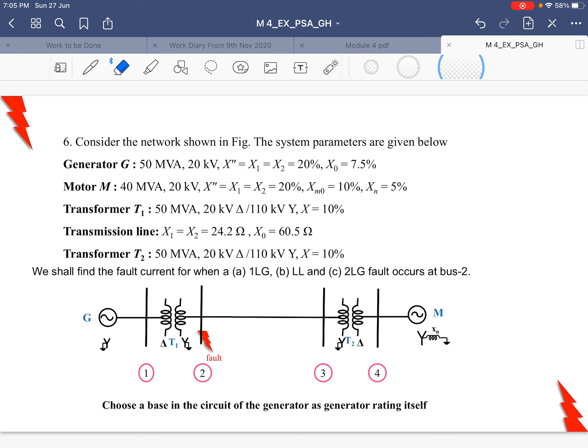What I have taken here is 50 MVA, 20 kV as the base quantity in the generator circuit. And here the transformer is 20 kV to 110 kV. The base voltage is transferred as 110 by 20 into 20, the 20 gets cancelled, so I get the base voltage as 110 here. Since there is a transformer on the other side, you transfer this 110 kV as 20 divided by 110 into 110, therefore it is 20 kV reflecting here. Means you are specifying the base quantities on all parts of the circuit wherever there is a partition due to the transformers T1 and T2.